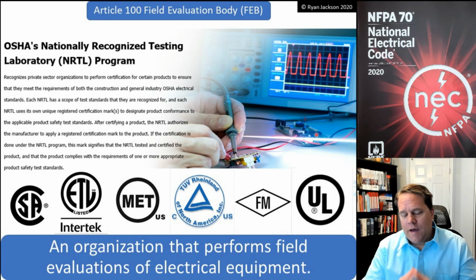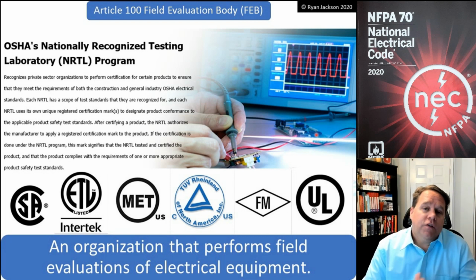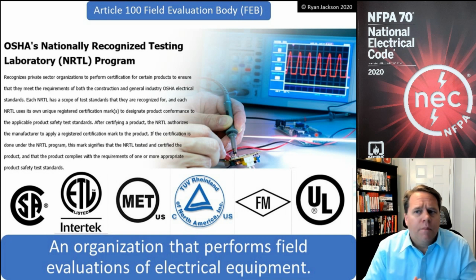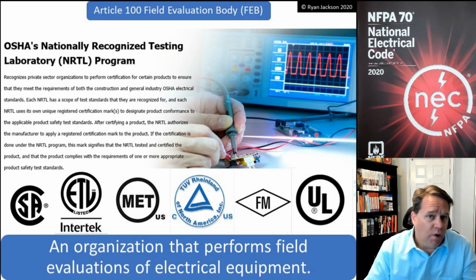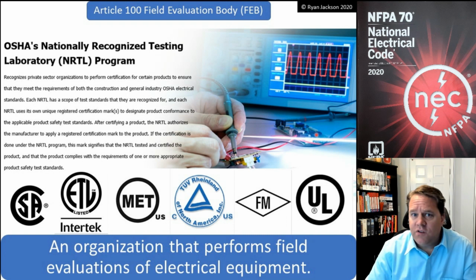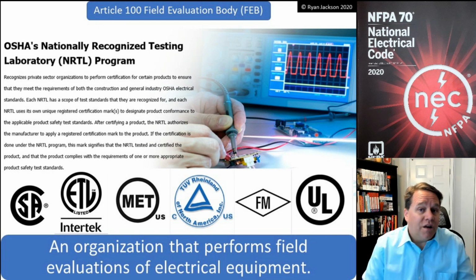What if I don't have a listed product? Well, first of all, not everything in the code has to be listed. A lot of things do have to be listed, but a lot of things don't. Under the 2020 code, believe it or not, circuit breakers don't have to be listed. As an inspector, I would expect to see a listed circuit breaker, but in the NEC, it's not necessarily required.